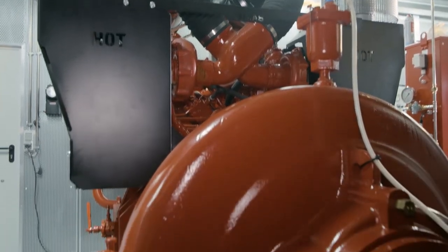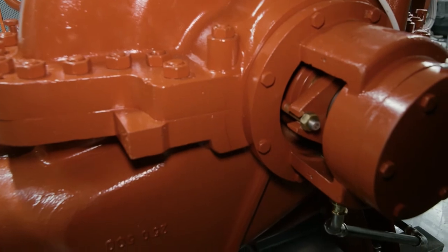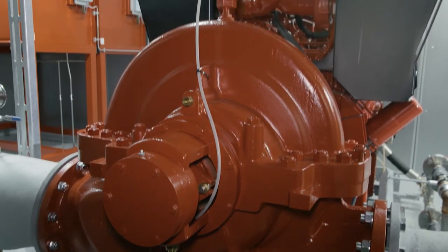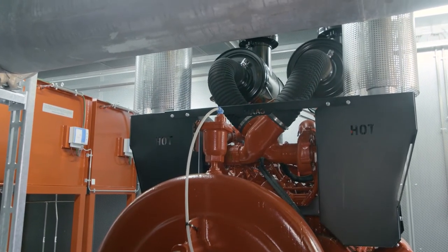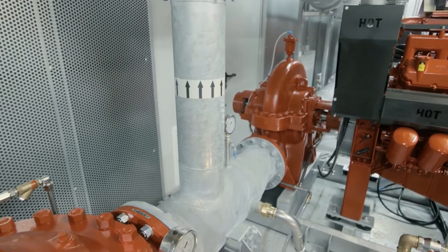A centrifugal fire pump with a nominal capacity of 1,300 cubic meters per hour at 13 bar. In emergency cases, the pump capacity is up to 1,800 cubic meters per hour. This high capacity is delivered by only one pump.